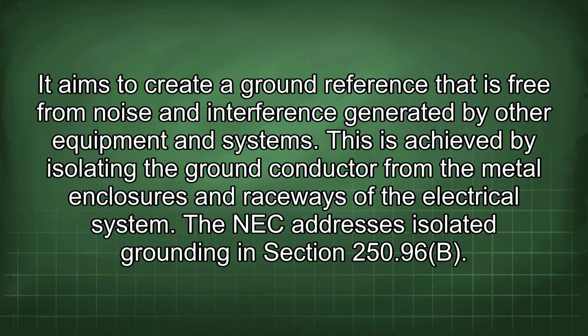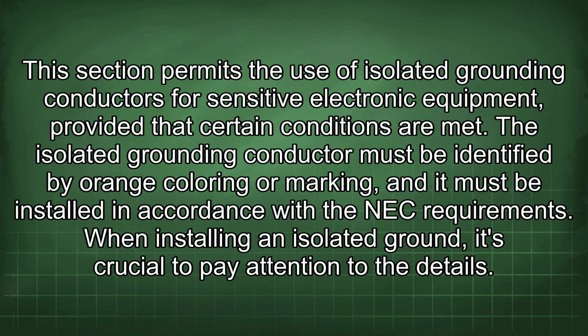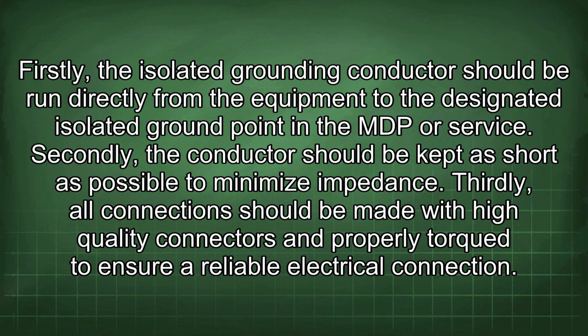The NEC addresses isolated grounding in section 250.96(B). This section permits the use of isolated grounding conductors for sensitive electronic equipment, provided that certain conditions are met. The isolated grounding conductor must be identified by orange coloring or marking, and it must be installed in accordance with the NEC requirements. When installing an isolated ground, it's crucial to pay attention to the details. Firstly, the isolated grounding conductor should be run directly from the equipment to the designated isolated ground point in the MDP or service. Secondly, the conductor should be kept as short as possible to minimize impedance. Thirdly, all connections should be made with high-quality connectors and properly torqued to ensure a reliable electrical connection.